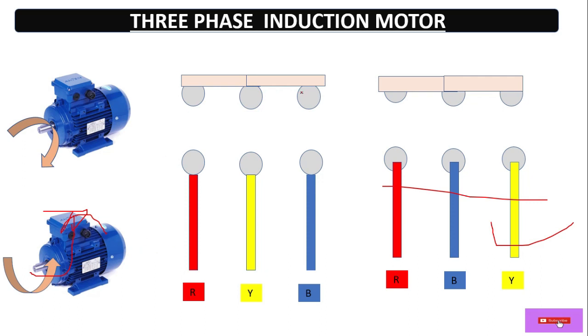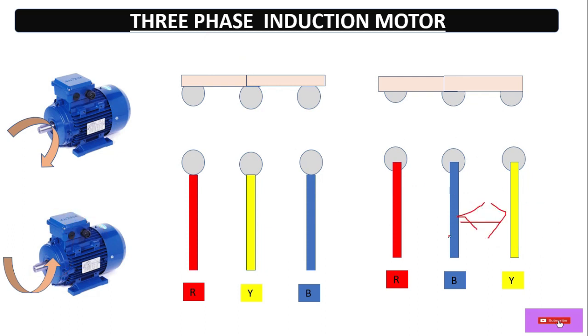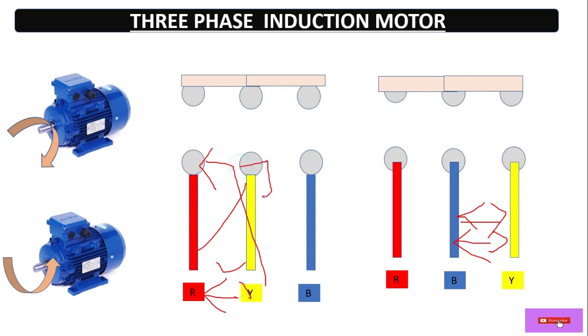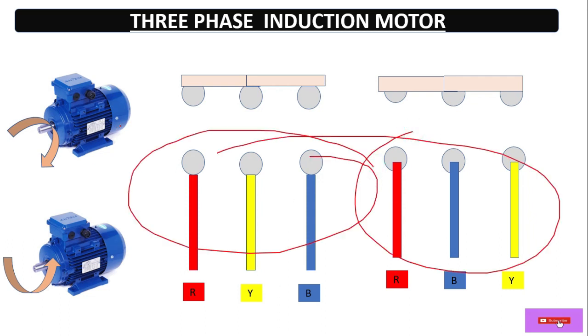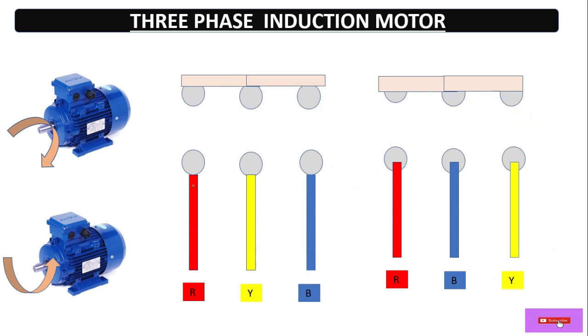In this way we can change the direction of the three-phase induction motor. Simply interchange the phase supply — exchange Y over here and R over here — in this condition also the motor will rotate in reverse direction. This is actually done with the help of a forward and reverse motor starter, DOL starter panel, with the help of the contactor. In this way we can reverse the direction of a three-phase motor.